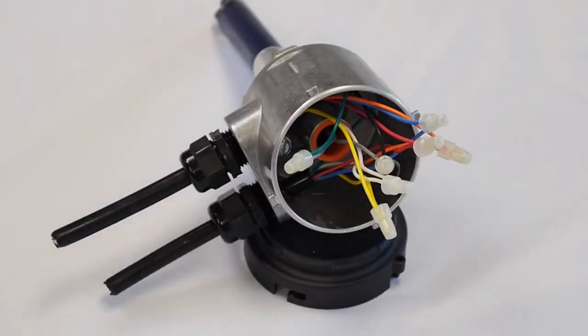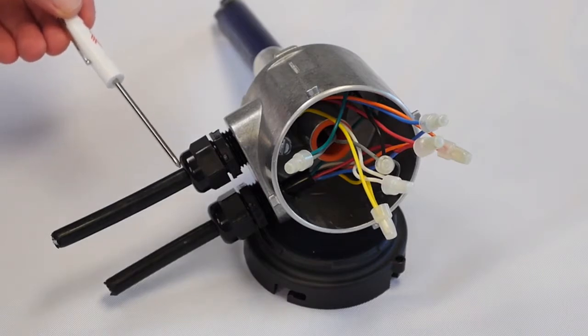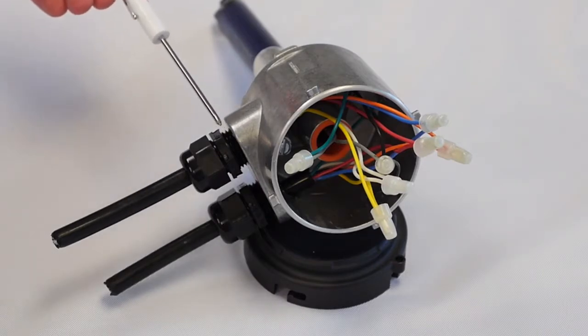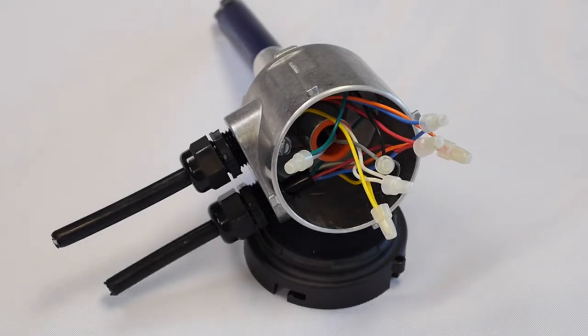Here we have an example of a typical 2-wire probe with all the wire connections stripped and crimped together. Just wanted to take a moment here to point out how important it is to make sure you have a good stripped and crimped connection, and make sure things like the strain reliefs are tight to the main wire cable and also to where it threads into the boss. You know, if moisture gets in here, it's going to create corrosion, and you're likely going to see an overfill issue that you're going to have to troubleshoot down the road. So quick recap, make sure that the cap seal is in good working order and you're getting a seal on the cap. Make sure your strain reliefs are good and tight.